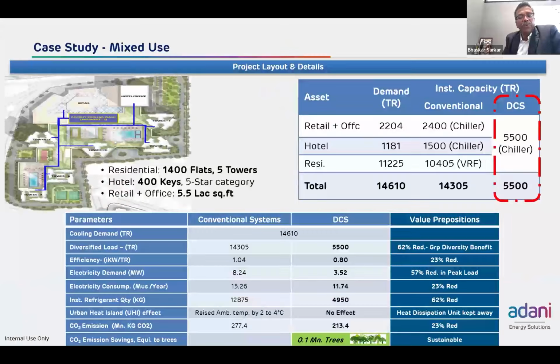Now, I'll touch upon a few case studies just to show the improvement. So this is a mixed case which we are implementing, where there is a significant mix of retail and office infrastructure, where there is a 2,200 TR demand. There is a hotel, there are residential accommodations. So the total cooling load requirement is 14,000. And had we installed chillers for the retail and hotel and also the VRF system, which was being planned, we would have installed 14,305 TRs of conventional capacity to meet this 14,600 TR of load.